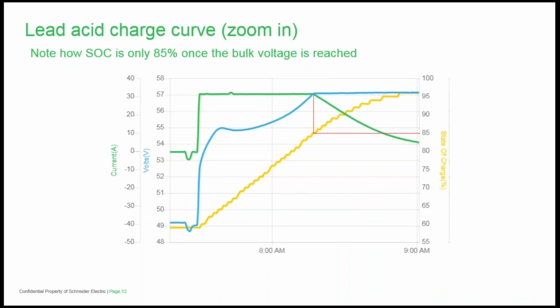So here we see load versus no load hysteresis of a typical lead acid battery. In bulk, the max charge rate is supplied to the battery until the bulk voltage is reached. At that point, the natural internal resistance of the battery requires less and less current to hold the batteries at the bulk voltage. Once the charge current drops to 2% of your declared battery capacity, and that's a settable parameter in our inverter and charge controllers, the charger exits the absorption stage, either to float, as in the case with the MPPT charge controller, or to no float with the inverter charger, assuming a grid interactive application.